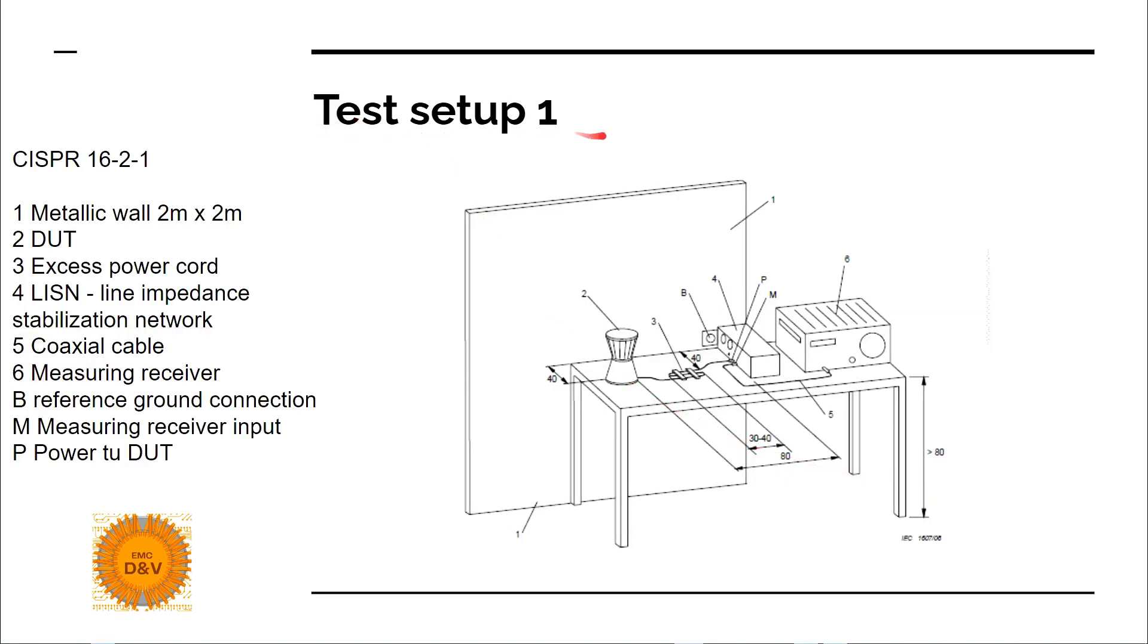Test setup example number one. This is an example of benchtop device testing. What is needed is a 2x2 meter metal wall as a low reference impedance for the common mode current return, usually made of stainless steel. And then a LISN, Line Impedance Stabilization Network, from which the device must be fed. It will provide a well-defined RF impedance for the DUT, device under test, and keep away unwanted interference from the mains and from the device to the mains.